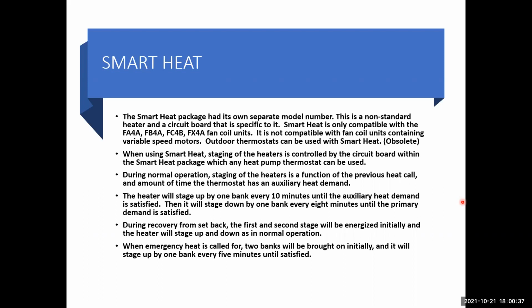During recovery from setback, the first and second stage will energize initially, and then the heater will stage up and down as in normal operation. When emergency heat is called for, two banks will be brought on initially, and it will be staged up by one bank of heat every 5 minutes until satisfied.